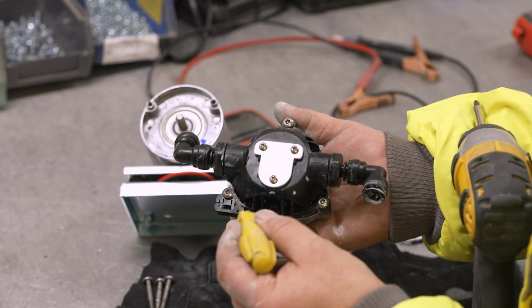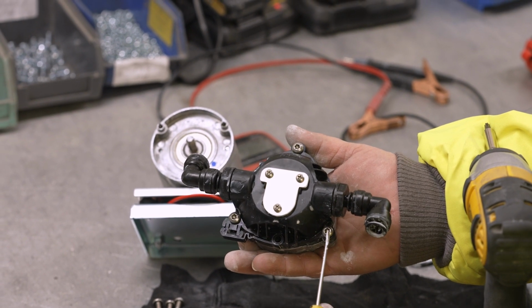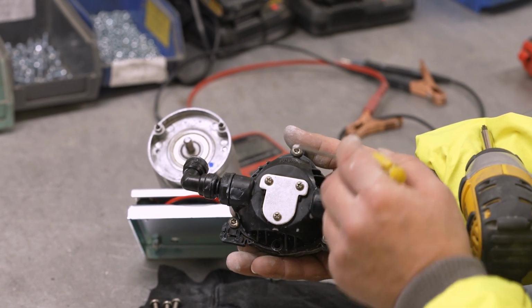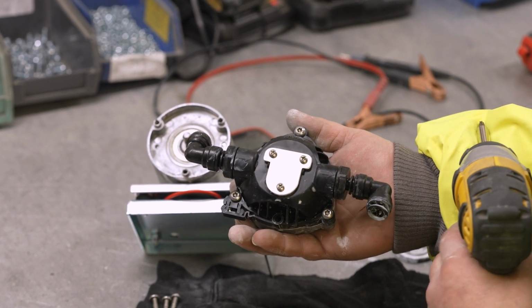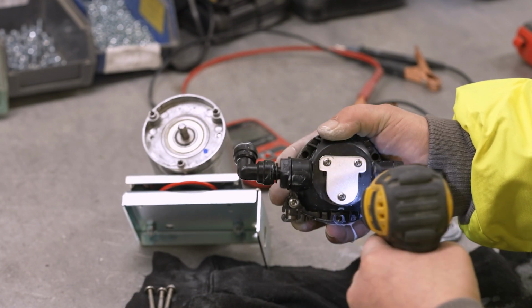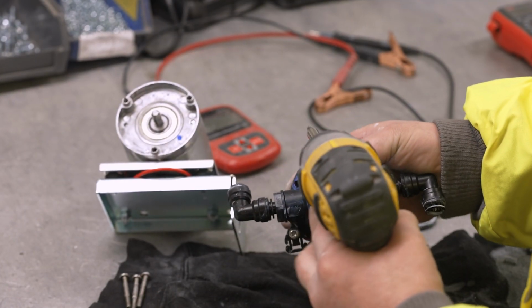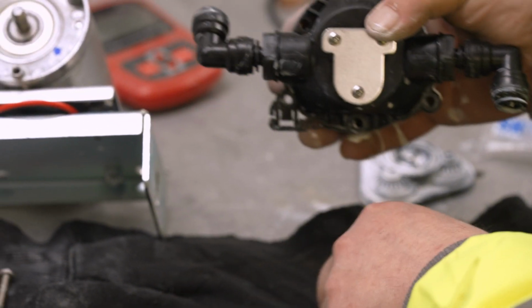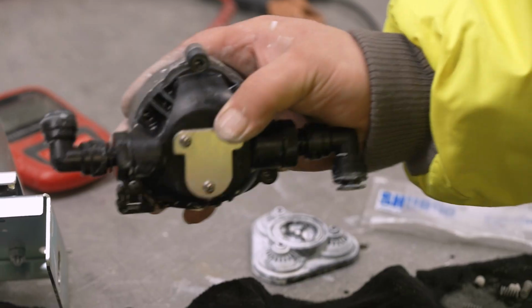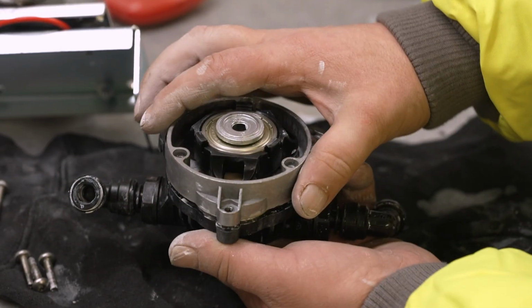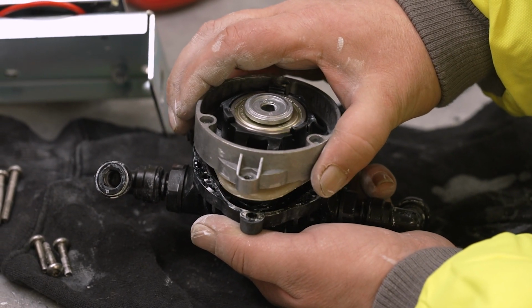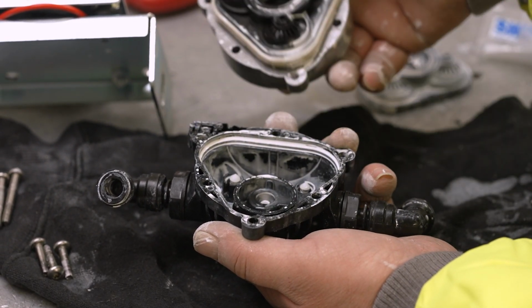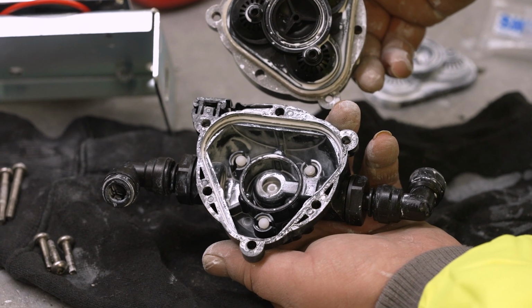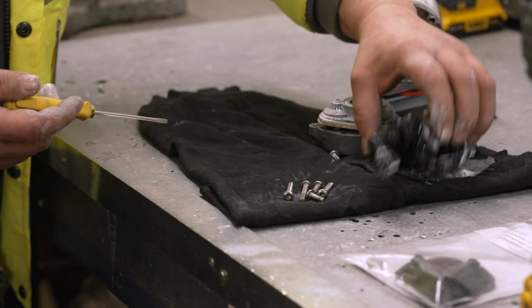Next, using the same T25 attachment, remove the 3 outer, short screws that are remaining to allow access to the check valve itself. It is recommended to do this in 2 stages to prevent the loss of small parts. Once done, carefully separate the top and bottom parts of the check valve. Inside the top black cap, you can see some very small plastic poppets and 3 small coiled springs.